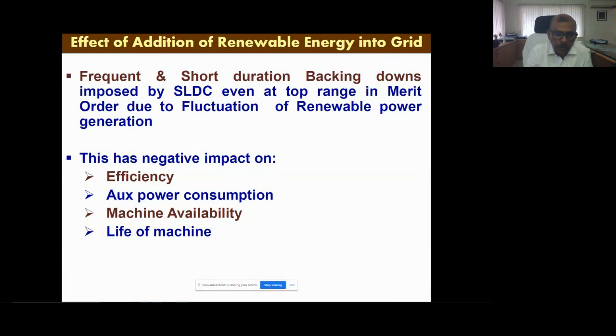Now, after moisture, the other factor affecting efficiency is frequent and short backing downs. Though we are not getting major backing down, because of the wind we are getting frequent and short backing downs from the load dispatch centers, which has a direct impact because of part load heat rate. As we all know, if you operate at 60%, the heat rate behaves badly and efficiency goes down. In this boiler we have to run all the auxiliaries even at 60-70% machine load, so this is increasing auxiliary consumption. Though machine availability is there, partial loading is increasing, and this is also affecting the life of the machine. This is common for all machines designed for base load operation, and so is the case with us.